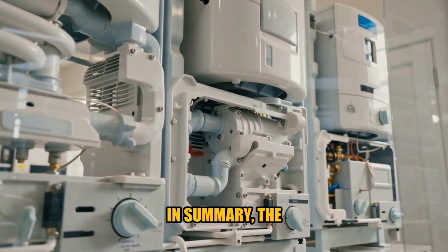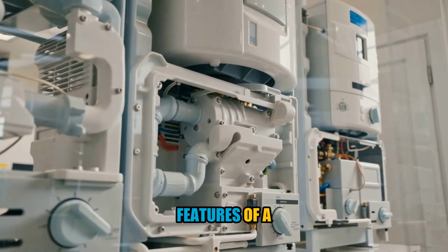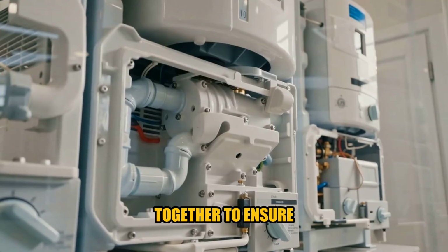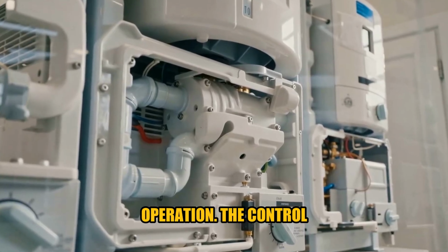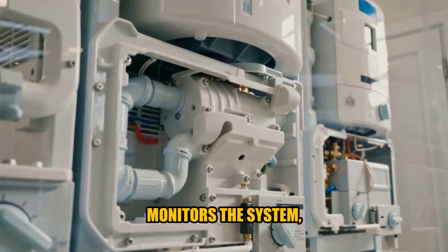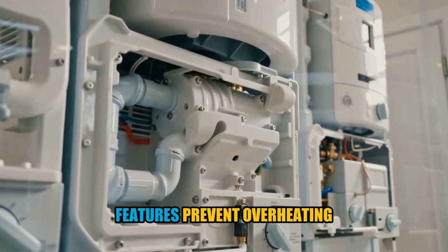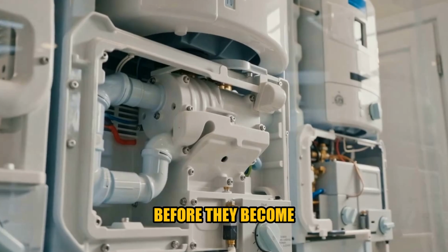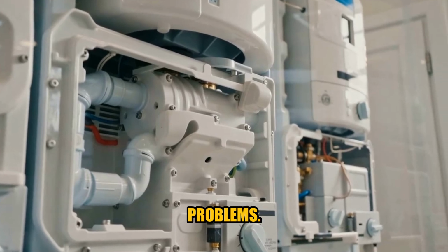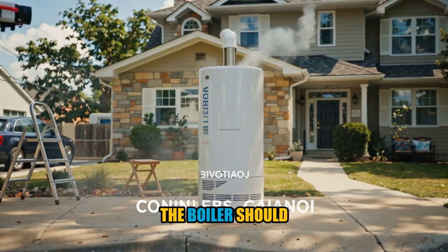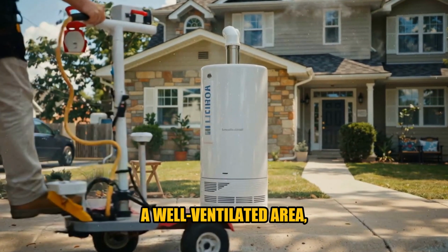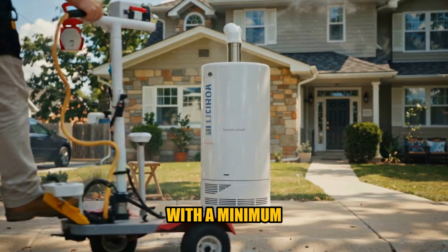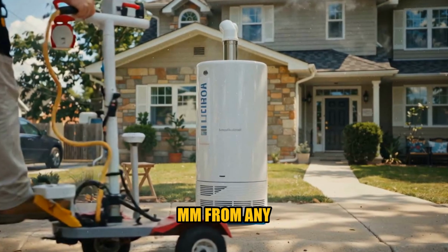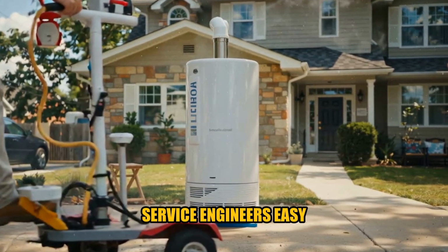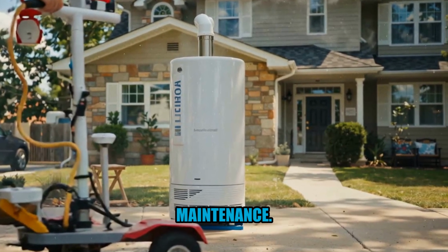In summary, the controls and safety features of a condensing boiler work together to ensure safe and efficient operation. The control panel regulates and monitors the system, while the safety features prevent overheating and catch faults before they become problems. Proper installation is crucial for efficient and safe operation. The boiler should be installed in a well-ventilated area with a minimum clearance of 300 millimeters from any combustible materials, giving service engineers easy access for future maintenance.